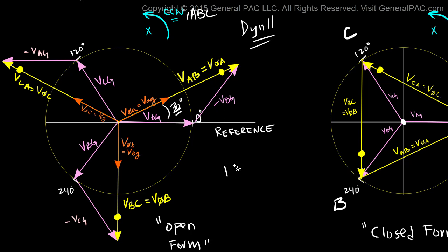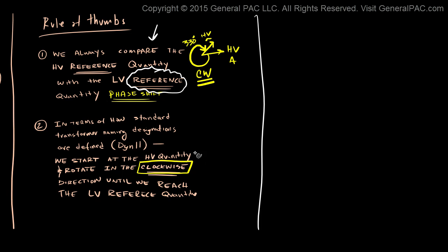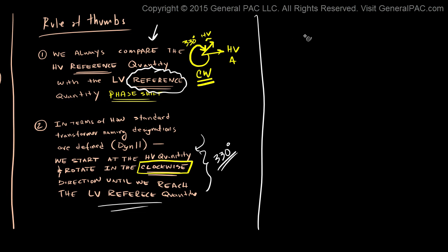That is what we're going to cover in Part 7E. In this video tutorial, we looked at these two rules of thumb: the first is that we're comparing the high voltage and the low voltage reference quantity; the second is that we start at the high voltage quantity and rotate in the clockwise direction until we reach the low voltage reference quantity. This implies a 330-degree phase shift. If you find this confusing, don't worry — there's a very easy way to digest this information, and that comes through the method of the clock system.